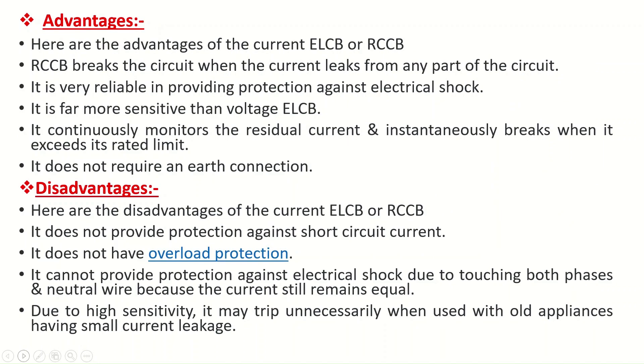Advantages of Current ELCB or RCCB: RCCB breaks the circuit when current leaks from any part of the circuit. It is very reliable in providing protection against electrical shock. It is far more sensitive than Voltage ELCB. It continuously monitors the residual current and instantaneously breaks when it exceeds its rated limit. It does not require an earth connection.